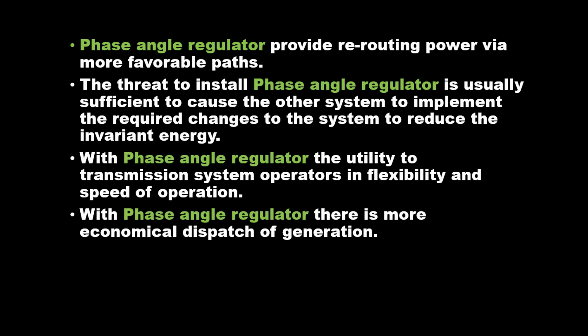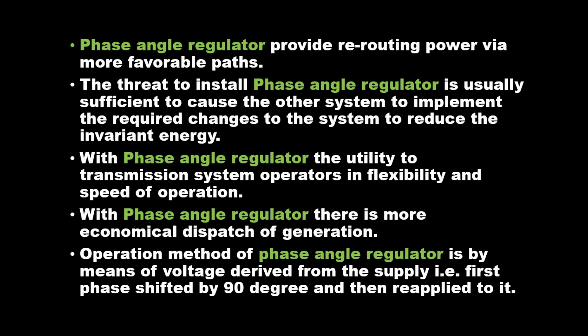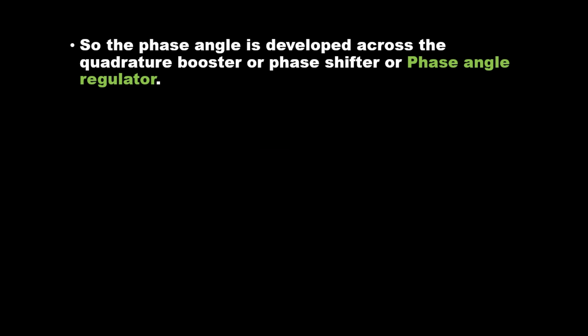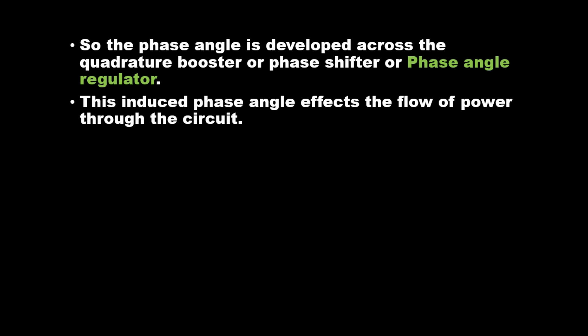The operation method of phase angle regulator is by means of voltage derived from the supply, first phase shifted by 90 degrees and then reapplied to it. So the phase angle is developed across the quadrature booster or phase shifter or phase angle regulator, and this induced phase angle affects the flow of power through the circuit.